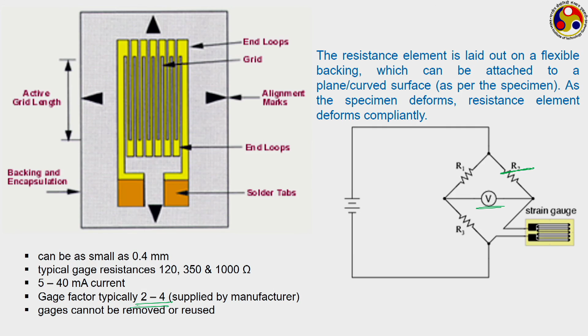These are certain typical features of strain gauges. They can be extremely small, often much smaller than a millimeter, depending on what value you want to measure. Typical gauge resistances are 120, 350 ohms or 1 kilo ohm, again depending upon what ranges of deflection you would like to measure. The current is at the 5 to 40 milliampere level. Most common gauges have gauge factors in the range of 2 to 4. This value comes directly from the supplier, and as I mentioned, gauges can't be removed or reused.